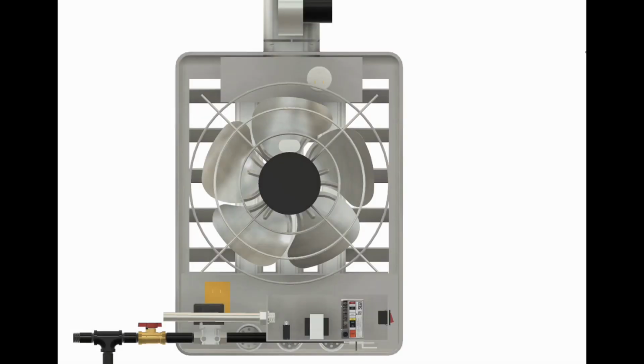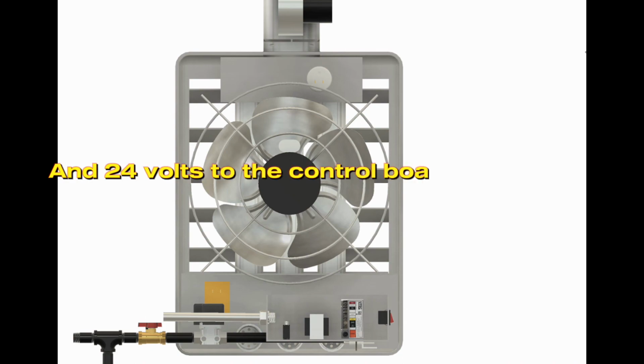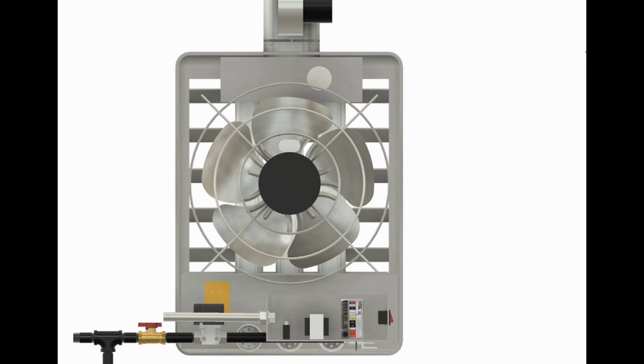And again, some of the main control components that we'll go over here. Power comes in. There usually will be a step-down transformer that steps down the incoming voltage down to 24 volts to power your thermostat on the wall. There'll be a fan relay usually. So when you provide 24 volts to the coil on the fan relay, the relay switches will close and send power up to the fan to start turning.